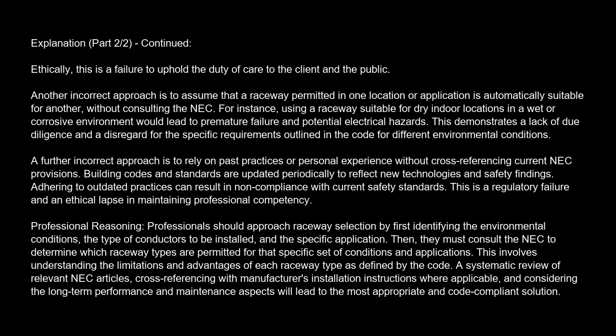Professional reasoning. Professionals should approach raceway selection by first identifying the environmental conditions, the type of conductors to be installed, and the specific application. Then, they must consult the NEC to determine which raceway types are permitted for that specific set of conditions and applications. This involves understanding the limitations and advantages of each raceway type as defined by the code. A systematic review of relevant NEC articles, cross-referencing with manufacturers' installation instructions, where applicable, and considering the long-term performance and maintenance aspects will lead to the most appropriate and code-compliant solution.